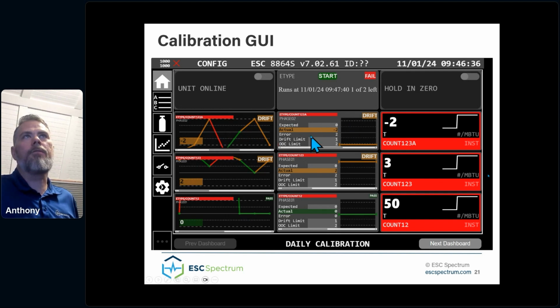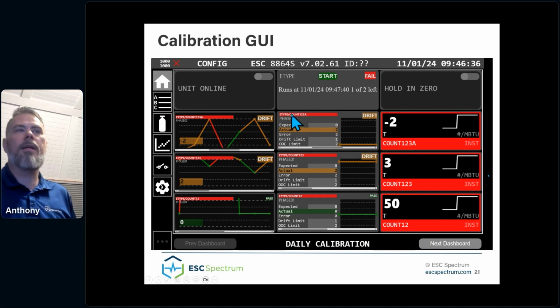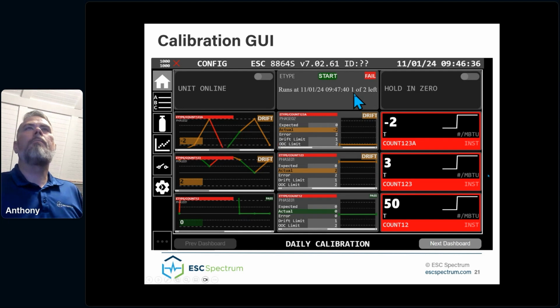So let's talk about the detail view. The detail view over here in the second column, again, the calibration and channel name is colored based on the worst status that occurred during the run, but the status of the current phase that you are looking at is shown over here on the top right. And again, you can switch back and forth between phases. The real difference between the trend and the detail is the detail will show you the results of the last cal run. Again, these are both not running. When it's not running, it'll show you the results of the last cal run that happened.